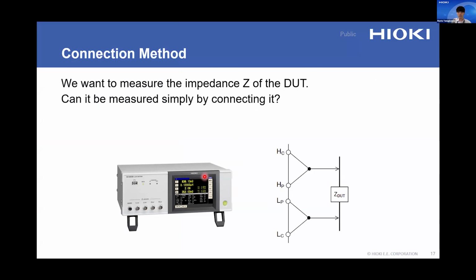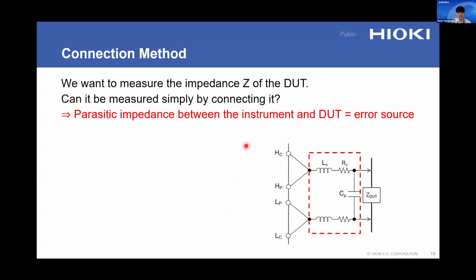For example, when measuring a DUT with a 4-terminal meter using the autobalancing bridge method, the DUT is connected using test leads. The way these test leads are connected directly affects measurement accuracy. It is not sufficient to simply connect the leads to both terminals of the DUT. The reason is that measurement leads and fixtures themselves have parasitic impedance like this. The lead wires have parasitic inductance and wiring resistance. And there is also parasitic capacitance between high and low terminals. In addition, contact resistance exists at the connection point to the DUT. To reduce these effects, the wiring method between the LCR meter and the DUT is very, very important.